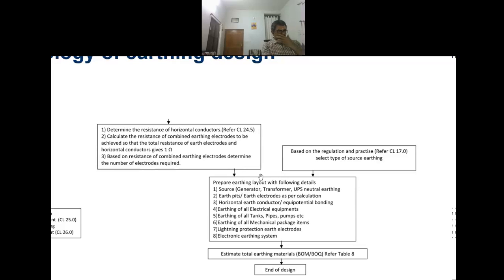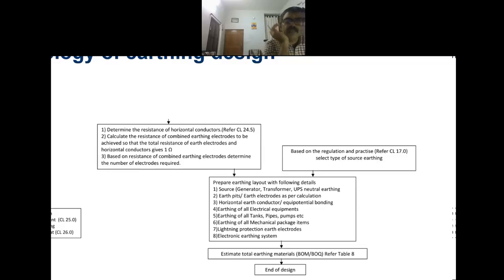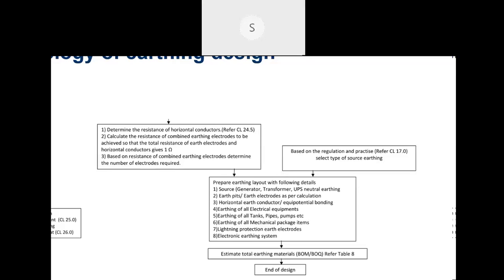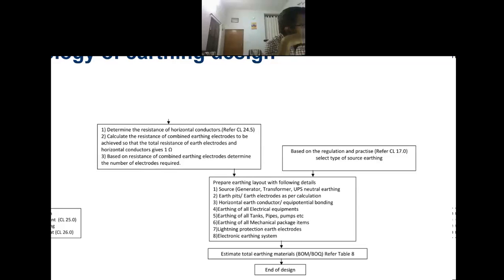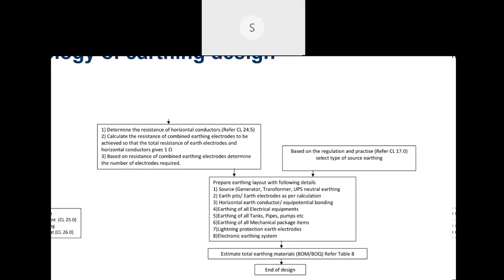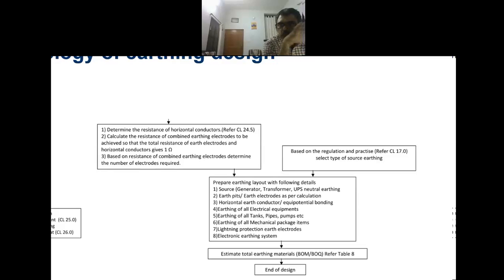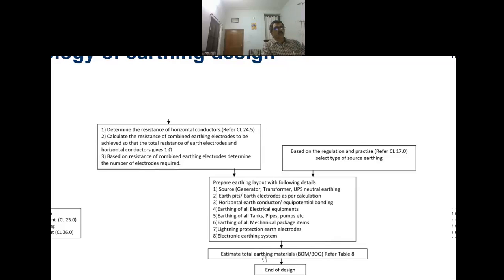Then we have to prepare a layout. When we do a layout, what all needs to be earthed? Transformers, any plant with steels, pipelines, containers, furnaces — all this needs to be earthed. And our panels, our electrical room, our UPS — all this needs to be earthed. Finally, we have to estimate the total quantity, for which we prepare the bill of quantity.